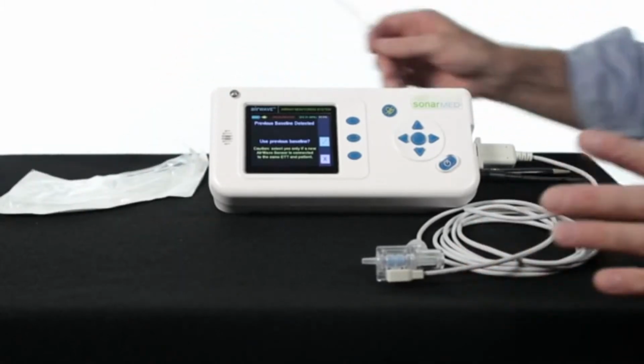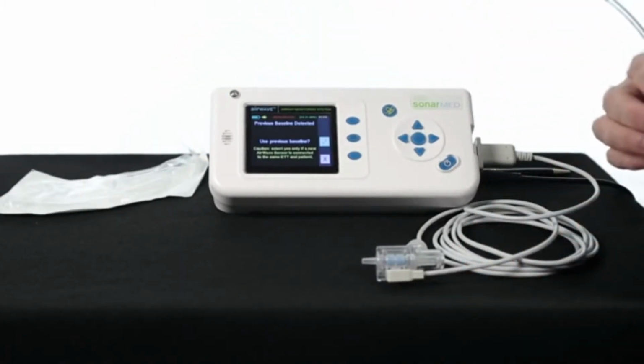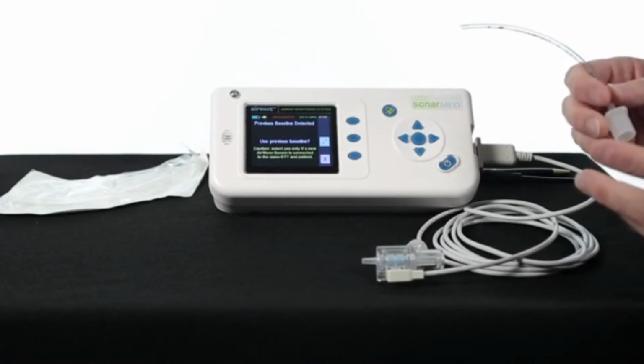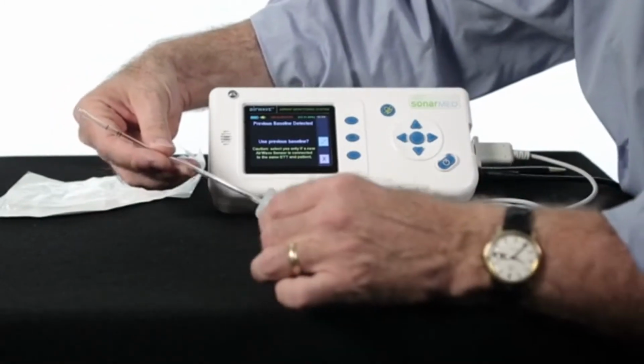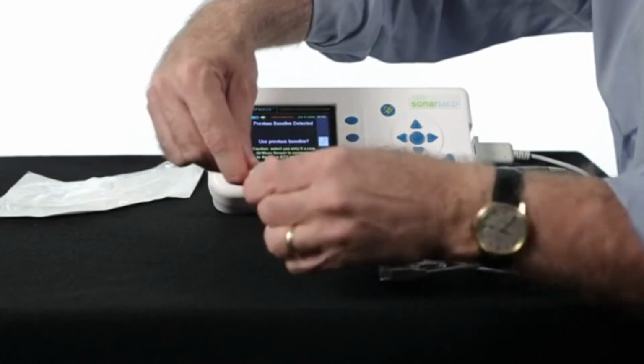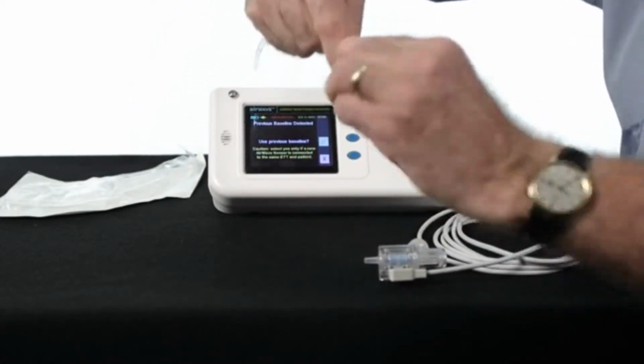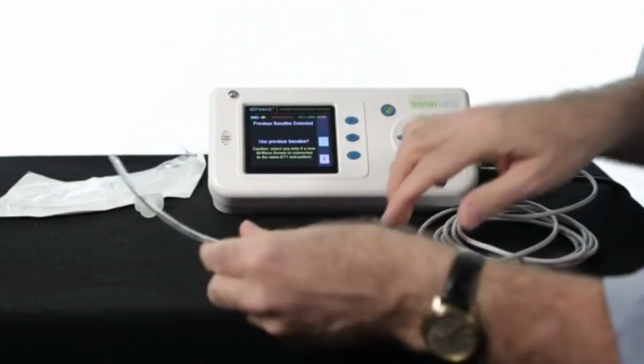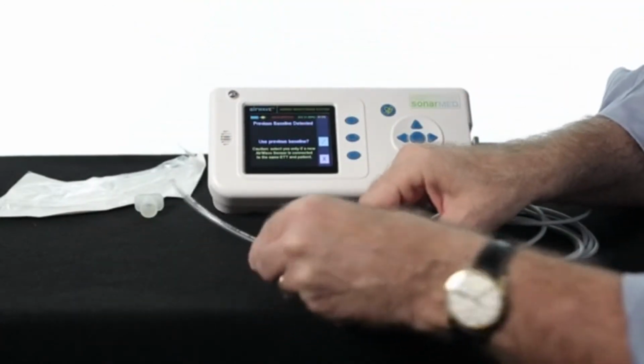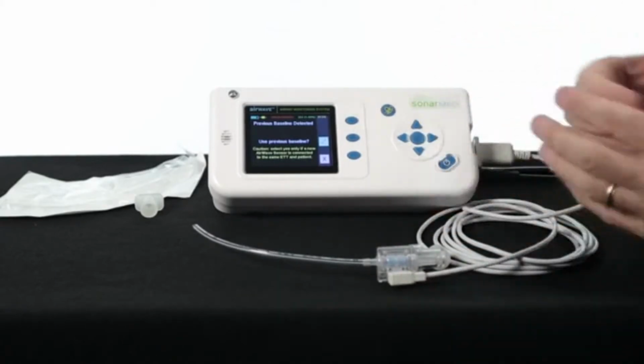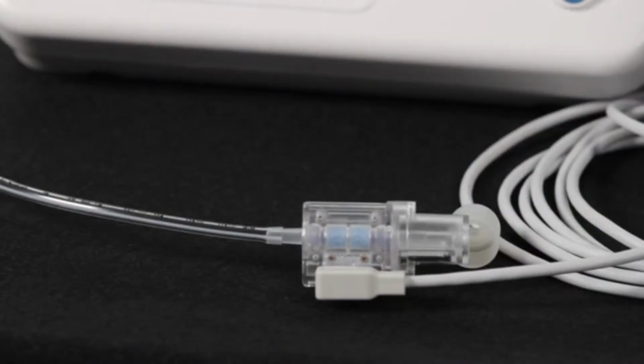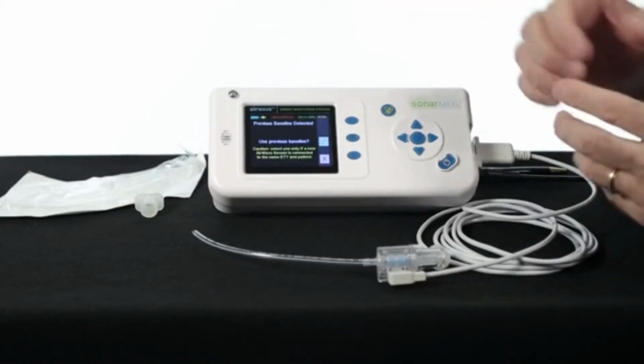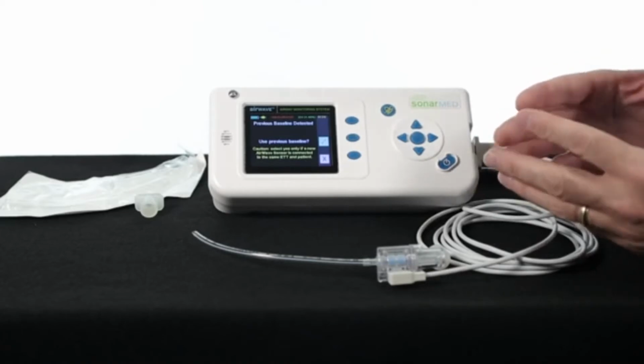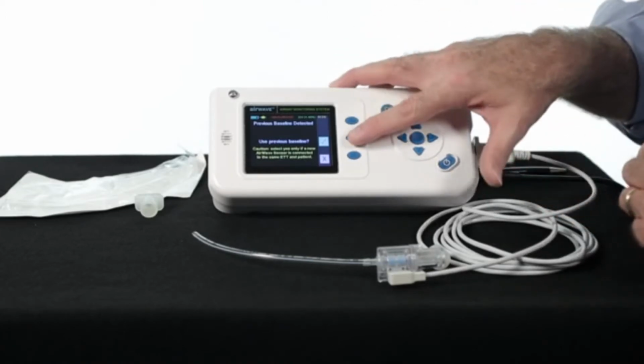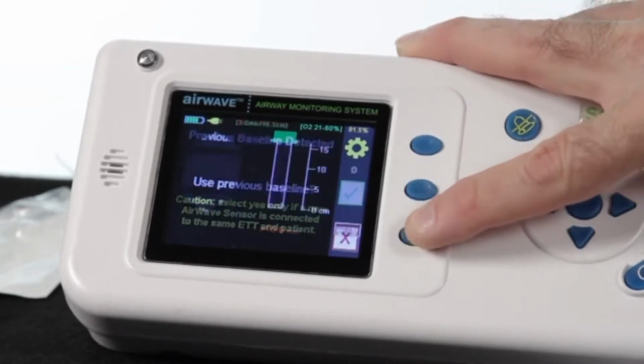The sensor can be used to intubate a patient, or it can be used on a patient that's already been intubated. In either case, you want to make sure that the adapter that comes on whatever endotrach tube you're using is removed. Once you remove that adapter, you hook the end of the sensor up to that spot. In this case, we could go ahead and intubate if we wanted to, or we could wait and set the baseline on a patient after they had been intubated. The question from the monitor now is, are you going to use the previous baseline? There is no previous baseline because this is a new sensor. So we're going to say no.